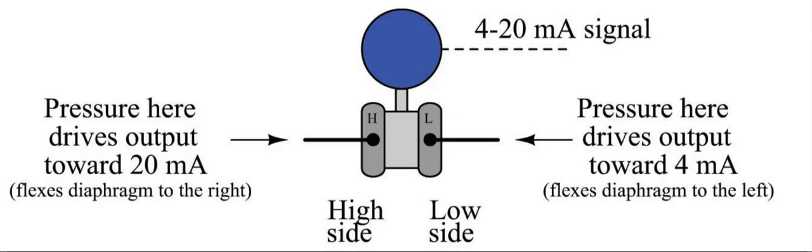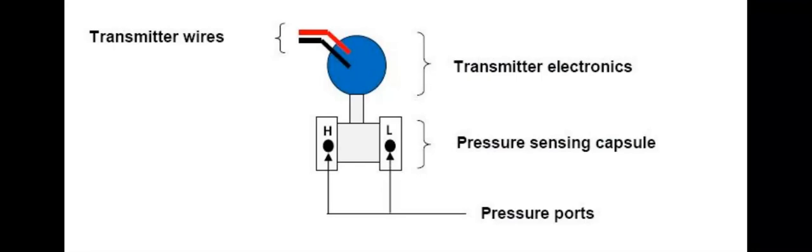For example, if the transmitter is going to read a range of between zero and two bar, zero being that the filter is clear and two bar being that the filter is blocking up, then this two bar range will correspond to a 20 milliamp output. So 4 milliamps is zero meaning the filter is not blocked, 20 milliamps would be the upper range value of two bar, and a 12 milliamp output would relate to one bar, which is halfway between. The electrical output corresponds to the amount of pressure difference applied across the differential pressure transmitter.